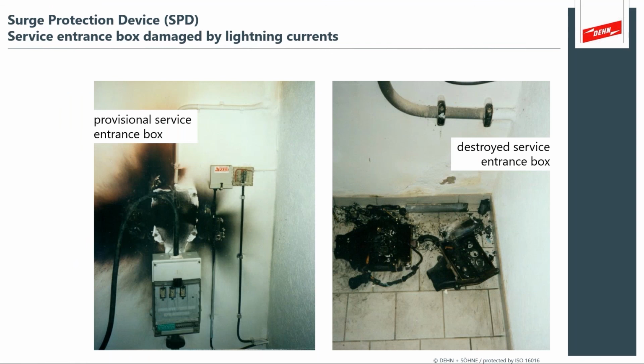So, features and benefits. Well, what's the benefit of having a large service entrance protection? Now you can control that voltage that might be coming in on the AC power or on the neutral ground bar. If the ground potential rises high enough, it still induces voltage and currents into your service entrance. And here you see what can result. Even with the application of surge devices, they can be undersized. Remember, we talked about applying these devices effectively. If you have a very high power AC service entrance with a very underrated device, you can have damage right at your service entrance.